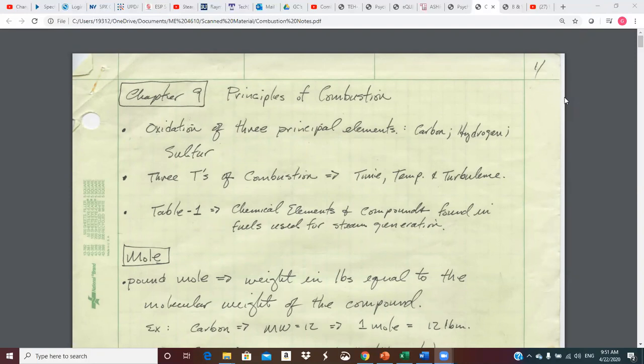We know that combustion is about oxidation. For a power plants person, it's usually a fossil fuel, and the fossil fuels when they burn — you're burning carbon, hydrogen, and sulfur. Babcock and Wilcox coined the three T's of combustion a long time ago. These are requirements to have effective complete combustion: time, temperature, and turbulence.